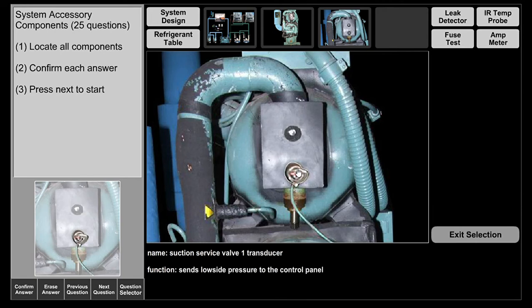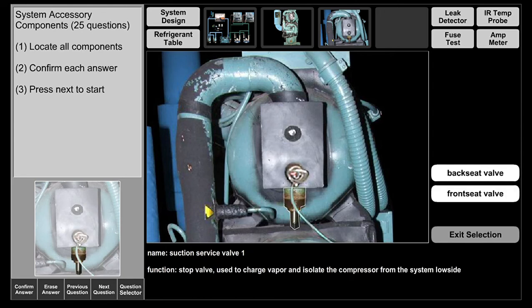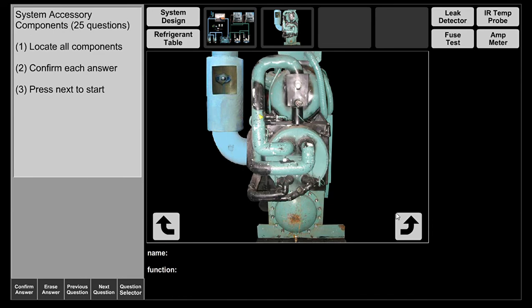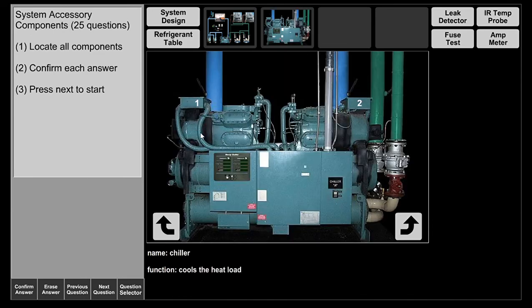At the compressor you have a charging valve, a transducer (pressure sensor sending a signal to the computer), and a service valve. The suction vapor enters through the back end of the compressor — through the motor — first, in order to cool the motor windings. Cold refrigerant vapor cools the motor windings, and then it proceeds into the pistons.